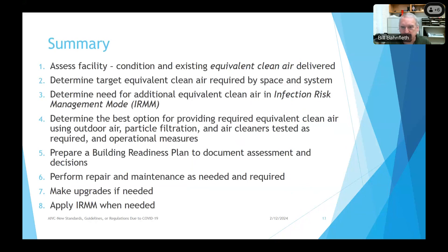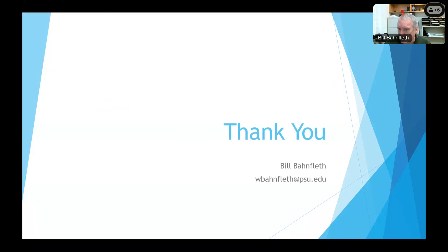To summarize, applying the standard involves eight steps: assess the facility to determine its condition and current equivalent clean air provided; determine the target for the space or system; if there is a gap, determine how to provide the additional equivalent clean air required; prepare the building readiness plan; implement it; perform repair and maintenance as needed; make upgrades if needed; and operate the system in infection risk management mode when needed. Thank you. I look forward to questions, and I'll pass it on to Jarek Kurnitsky from REHVA to talk about European standards.